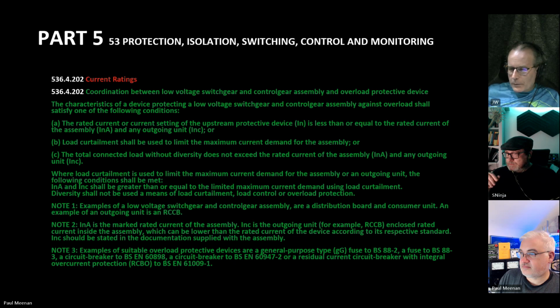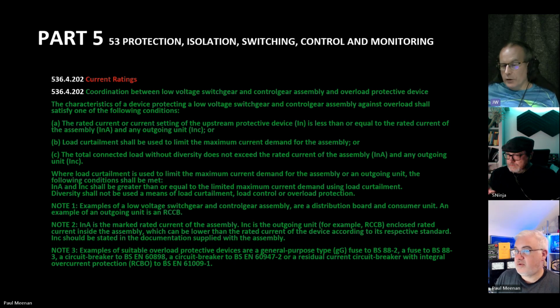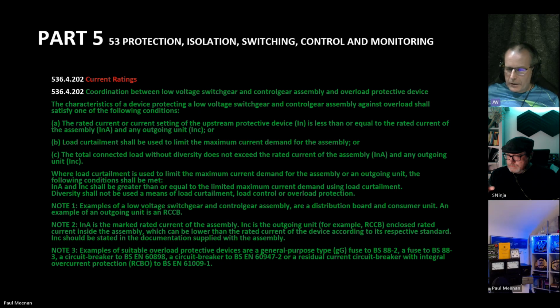So what we've got then is the characteristics of a device protecting a low voltage switchgear and control gear assembly against overload shall satisfy one of the following conditions. A, the rated current or current setting of the upstream protective device is less than or equal to the rated current of the assembly and any outgoing unit. Or B, load curtailment should be used to limit the maximum current demand for the assembly. Or C, the total connected load without diversity does not exceed the rated current of the assembly and any outgoing unit.